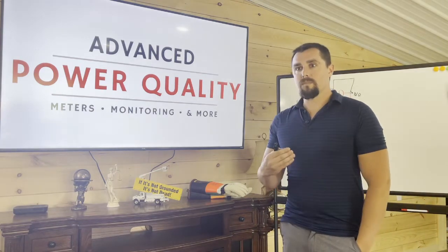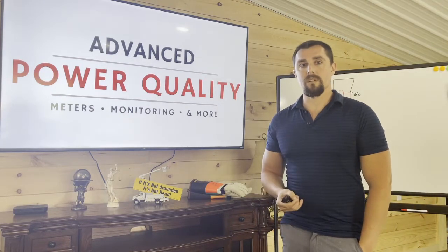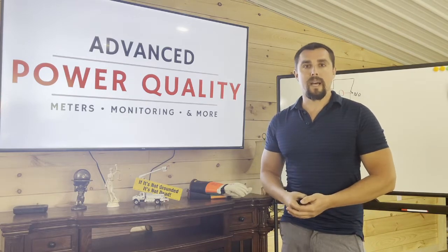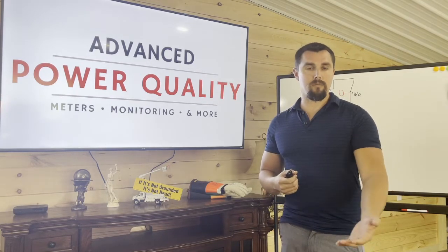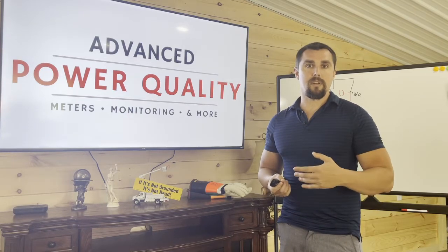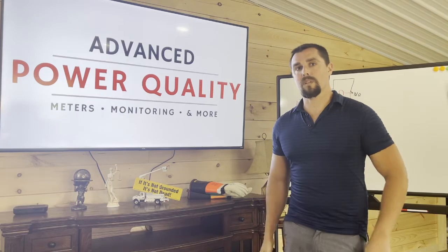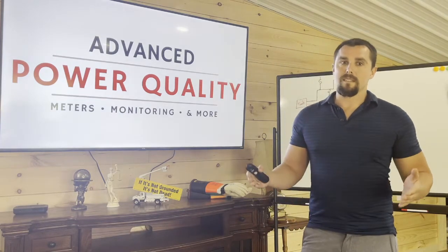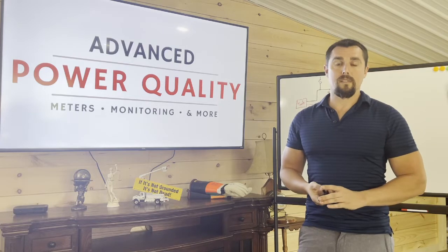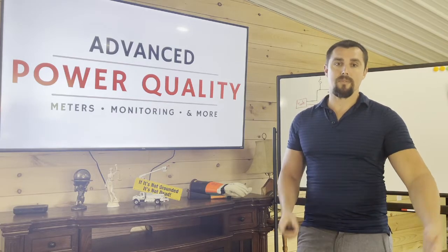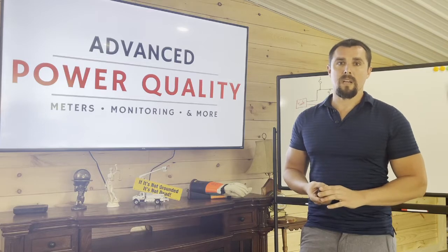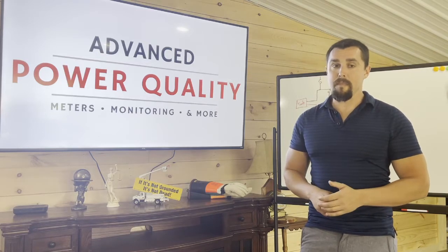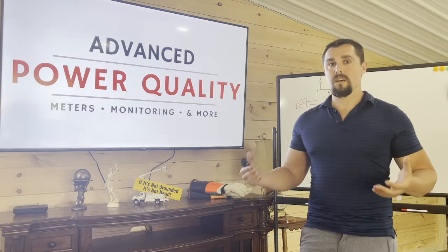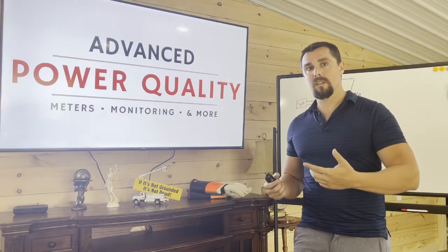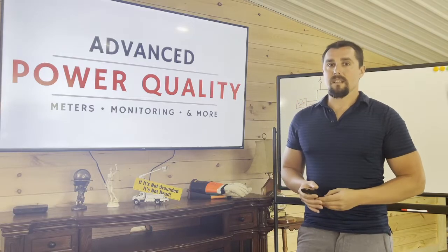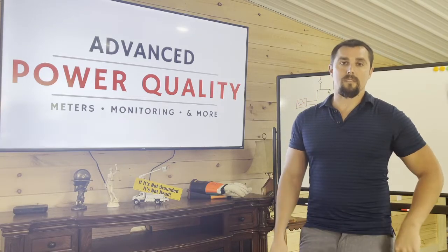Whenever a customer is thinking of these items, a lot of customers have generator backups. Well, customers need to realize that the generator ramp up time is normally about 8 to 10 seconds. That 8 to 10 seconds may kick off a lot of their equipment. A lot of equipment can't ride through 10 seconds of no power. The only thing that may be able to is really large industrial motors with that rotating inertia. And again, 10 seconds is asking a lot of your equipment to ride through that event.